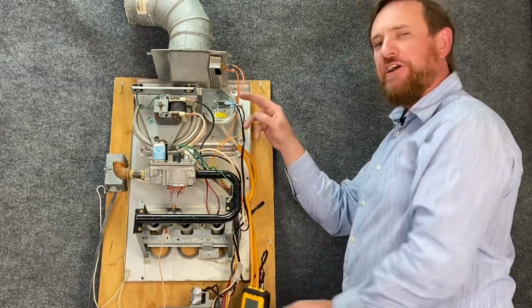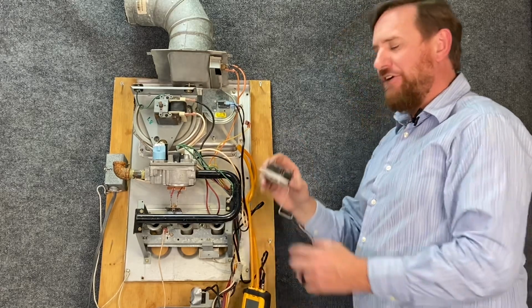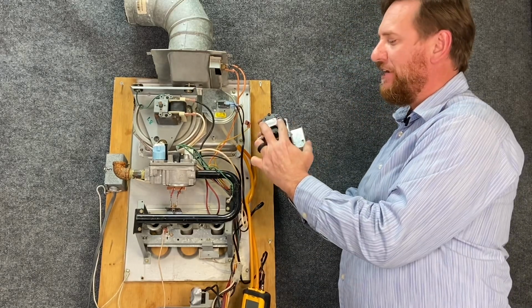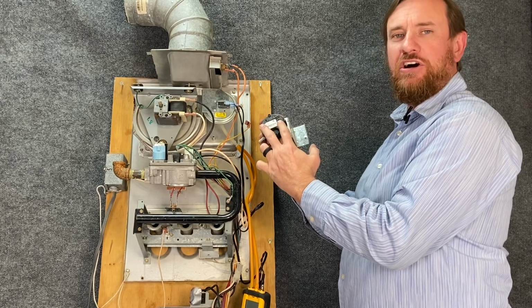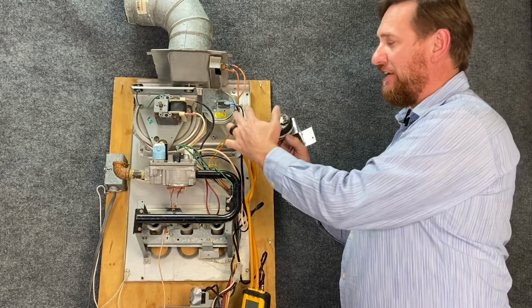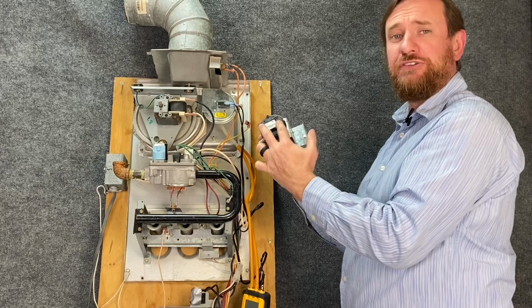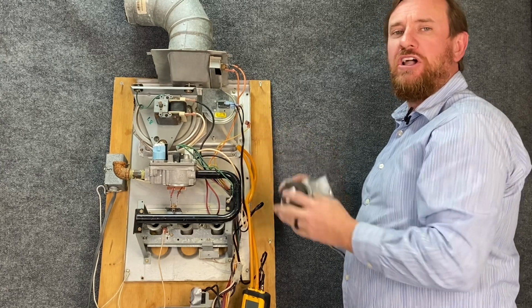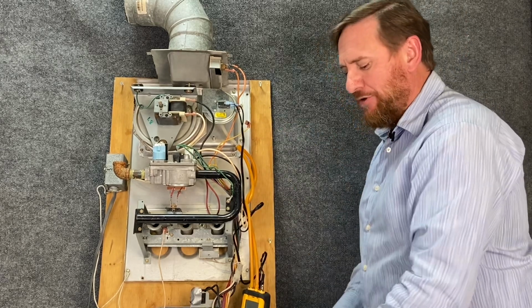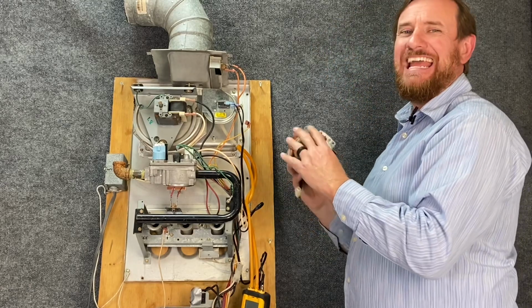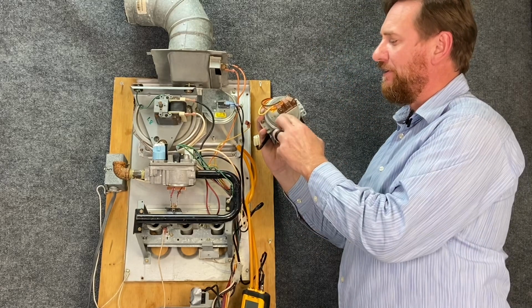Now most of these pressure switches are NO. NO stands for normally open. So if I check these two, they're normally OL, infinite resistance. If I check it on the unit, I have 24 volts or some kind of voltage. But not all of them are normally open. They do make some that have normally open and normally closed connections, such as this one.